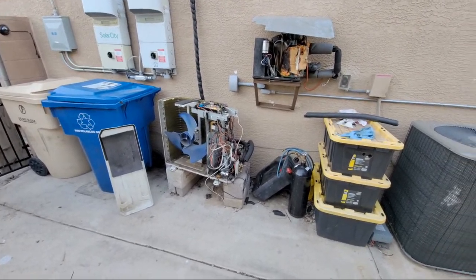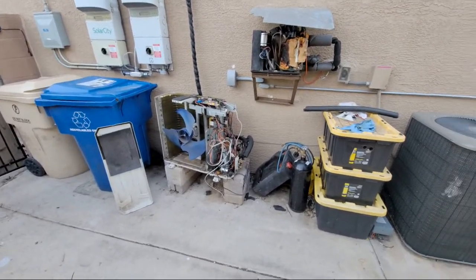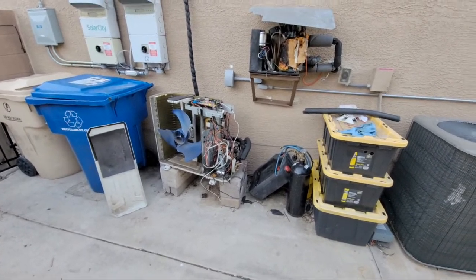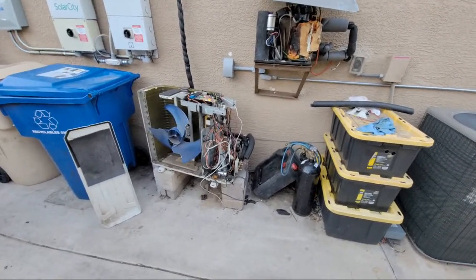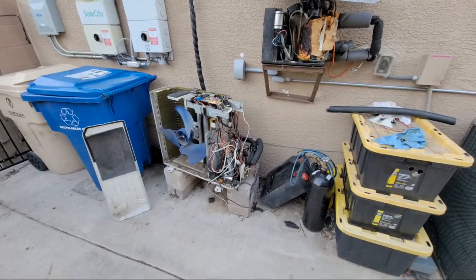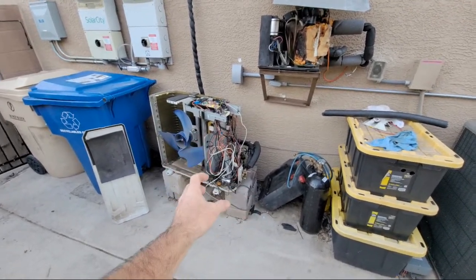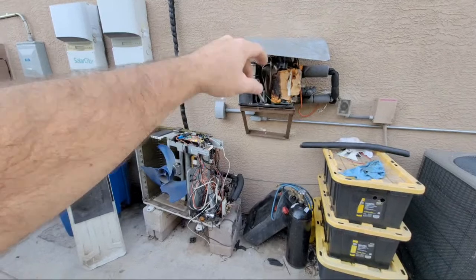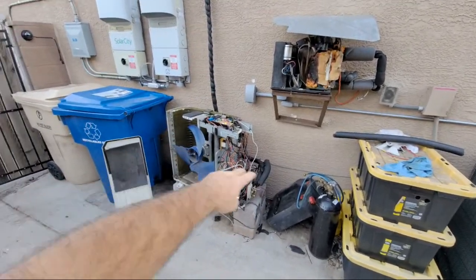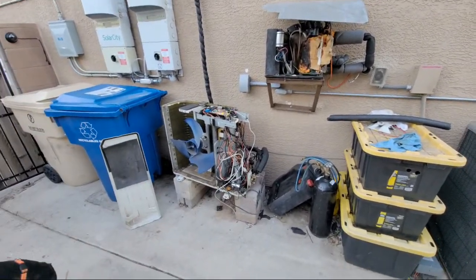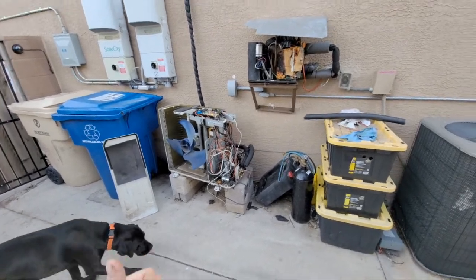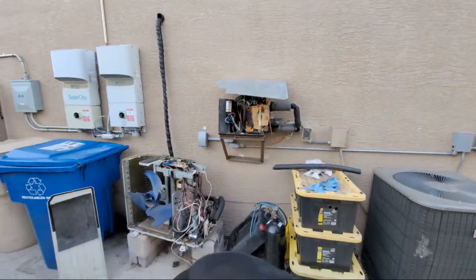The water temperatures are kind of elevated for what you'd think you're going to heat. So at 105 degrees, he's like, do you need it hotter than that? I think with just the small compressor, with the additional lines and the additional circuit of the condenser, it just wasn't efficient to create heat into that heat exchanger and heat the water.